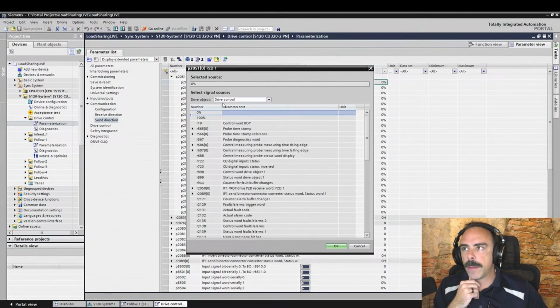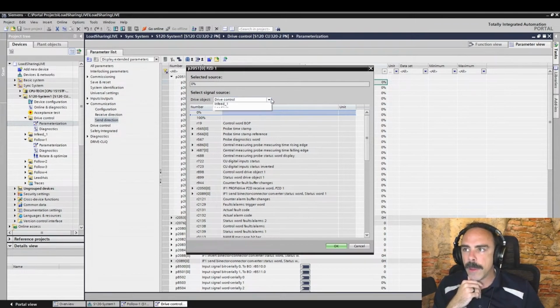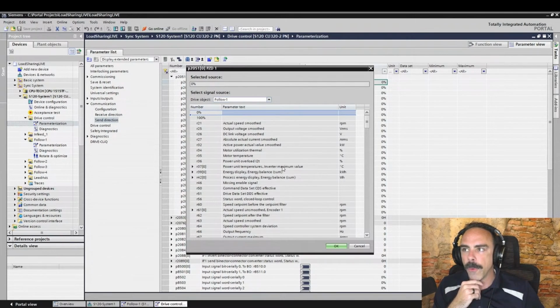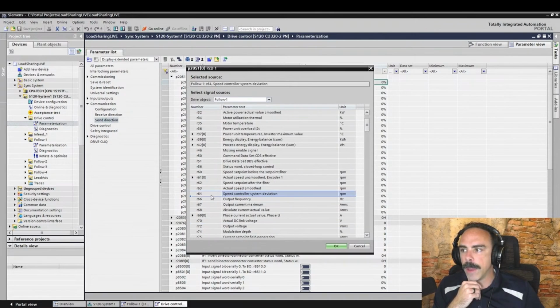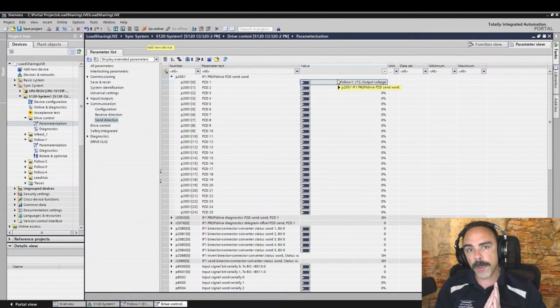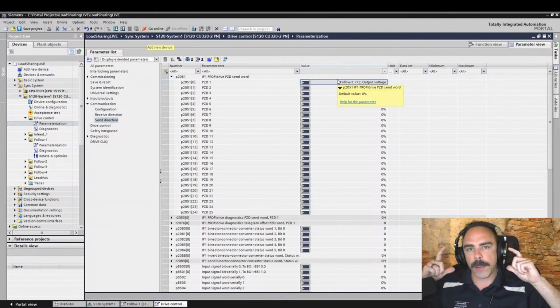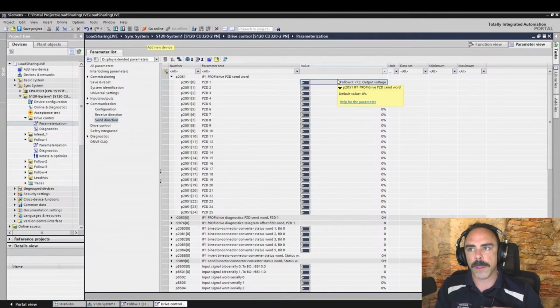See, this is just the drive object for drive control. Thing about the S120 is all of these parameter sets exist on the same hardware. So let's just go to follower 1 and get that r72 value that we were wanting and plug it in. And now that data coming across from the control unit telegram is actually coming from the follower axis. So another axis.